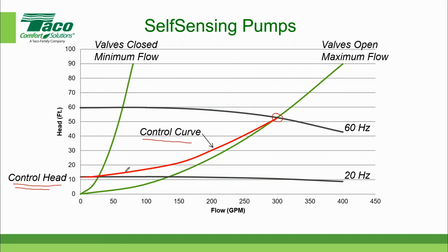The control curve is relatively flat at this part of the curve here. So the control head is virtually the same value as the pressure differential at minimum flow. Let's assume for a moment that my minimum flow in this case is 25 gallons per minute. Let's just arbitrarily draw a line right there. At 25 gallons per minute, the control curve is virtually flat or horizontal. So the control head is the same value as the pressure. I'm just going to make up a number and say that's roughly 12. So the control head in this case is 12 feet approximately. I'm reading it off my simplified chart here. That happens to be the same pressure differential at minimum flow.